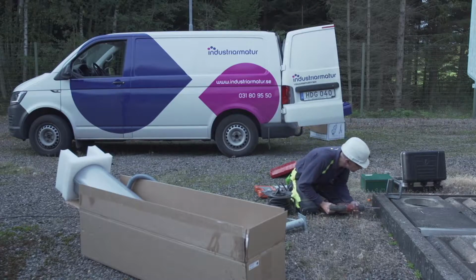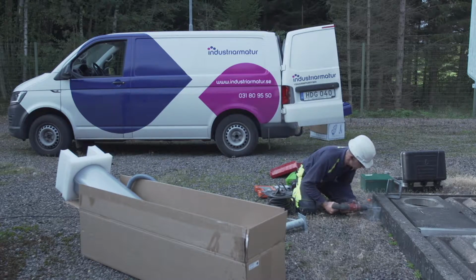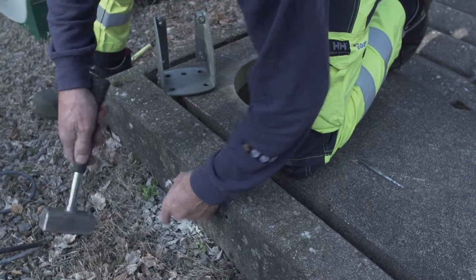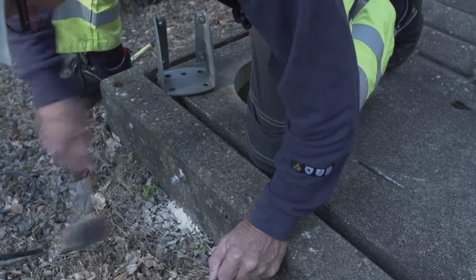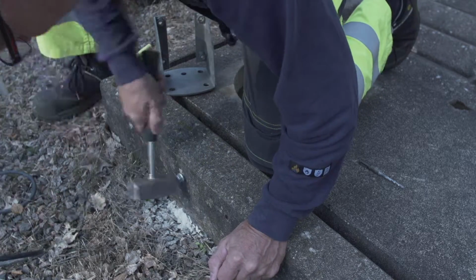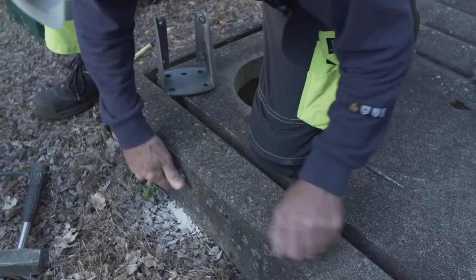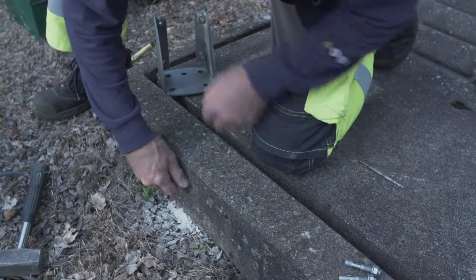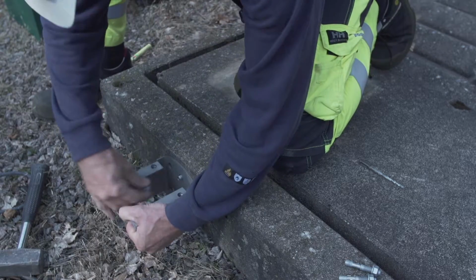Mark the holes and then drill a 55 mm deep hole using a 10 mm concrete drill. Knock in an expansion bolt so that it bottoms and about 15 mm protrudes. Let the nut remain in place when the bolt is knocked in. Weigh and adjust if necessary with a hammer.